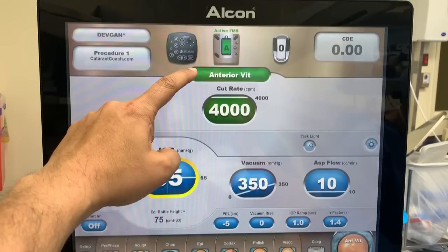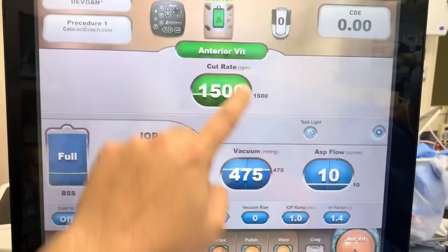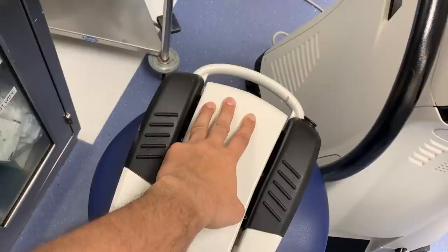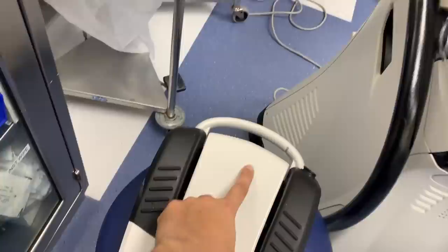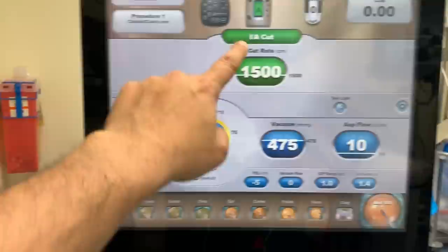On this phaco machine, there's an anterior vitrectomy mode with two sub-modes: anterior vit and IA cut. In anterior vitrectomy mode, pedal position one is infusion/irrigation, two is the vitreous cutter, and three is aspiration. In IA cut mode it's different: position one is still irrigation, position two is aspiration or vacuum, and position three is the vitreous cutter. The order of functions is distinct between the two sub-modes.